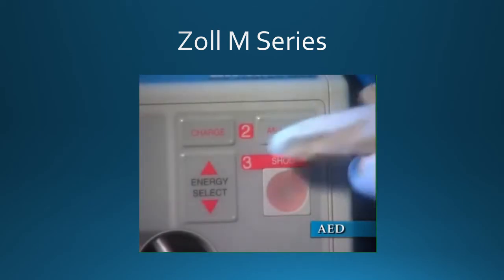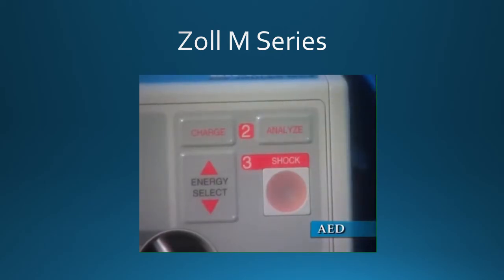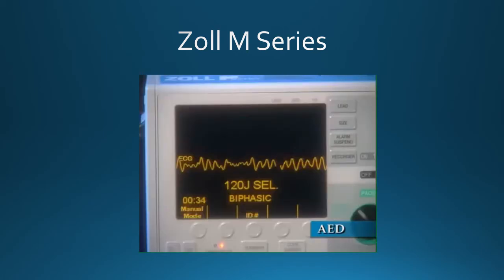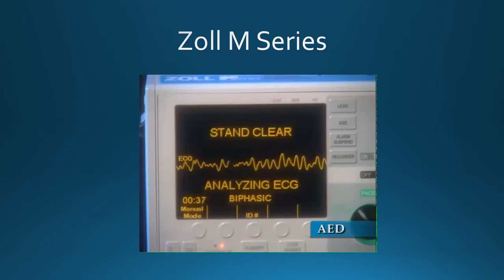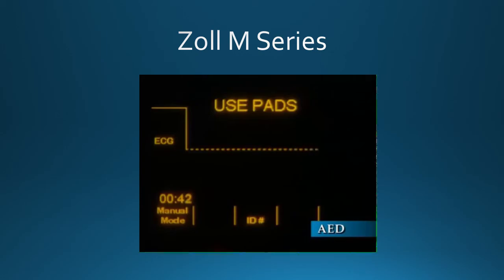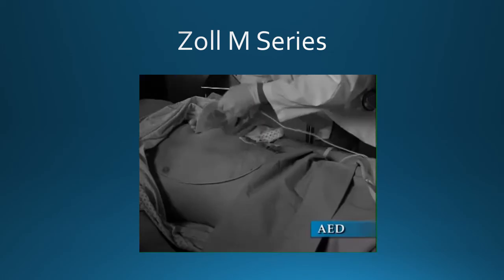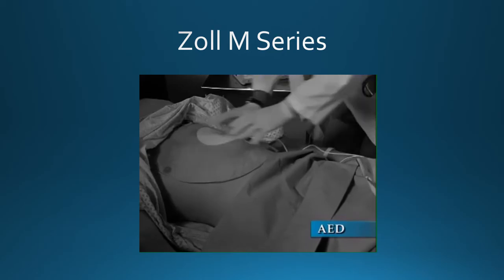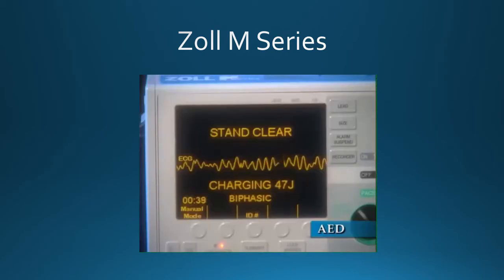Press the Analyze button to begin the analysis of the patient's ECG rhythm. Stand clear. A Stand Clear message and voice prompt will be issued. An Analyzing ECG message is then displayed while the patient's ECG is analyzed. If MFE pads have not been properly connected to the patient, a Use Pads message will be displayed and analysis will be inhibited. Warn all persons attending the patient to stand clear. No one should touch the patient, bed, or any equipment connected to the patient during defibrillation. A severe shock can result.